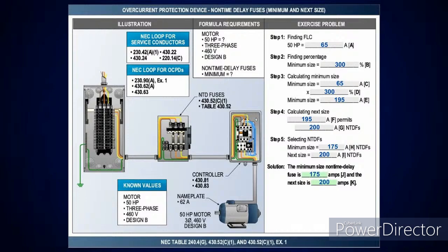Now, you've probably seen some of these arguments on the groups and stuff, and they try to tell you there's no such thing as a minimum. What the minimum is, is a starting point. Okay. And I give a good example of this: if you go over in the 2023 and you look at 440.22(A), they added text in there, and it looks just like motors. And what I always tell everybody is when you go look at a nameplate, how many times have you looked on there and you have a HACR breaker rating for that AC unit and it has a minimum and a maximum? That is a terminology that has been used, and we've been doing this forever this way.